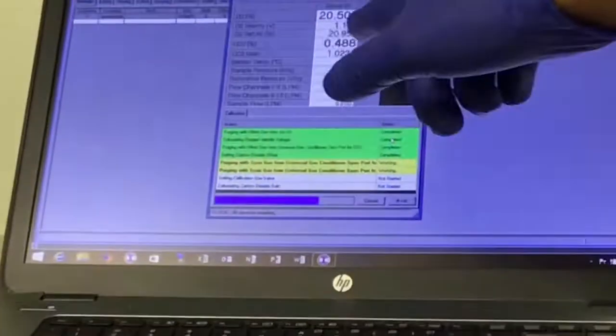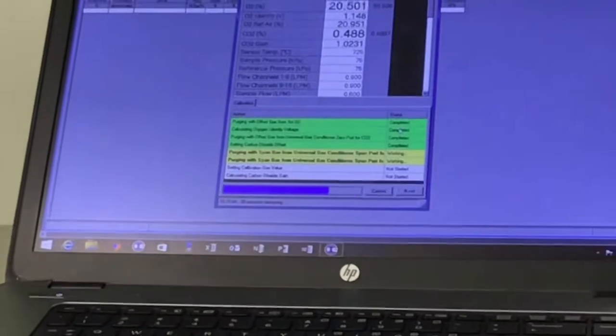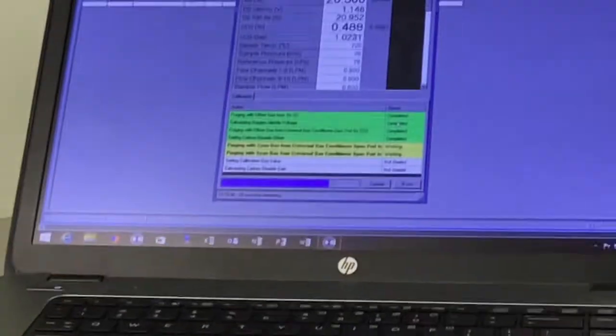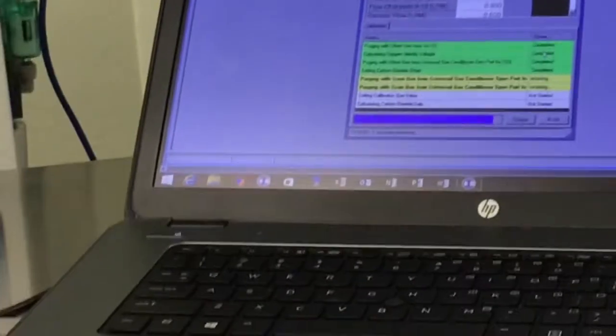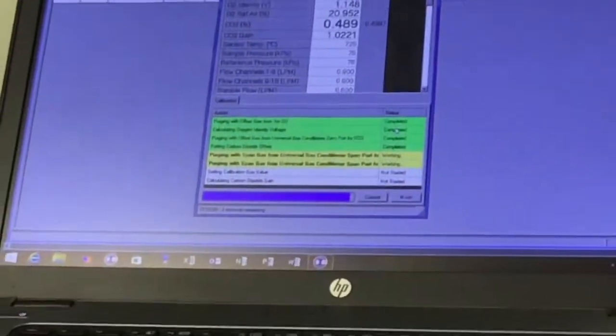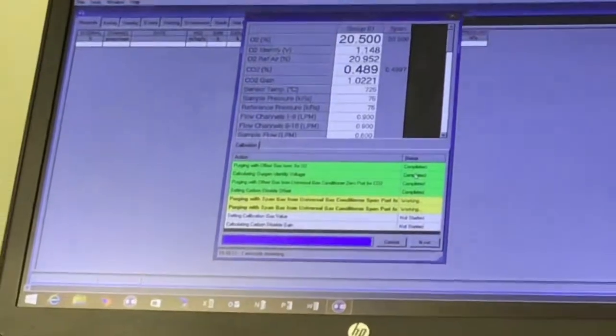Especially the last step is just calculating the gain. The important thing about calibration is that at the end, it should never say it failed. The first thing to look at is the 10 psi, that the gas is plugged in. If you have a calibration process where the gas is on at 10 psi, and you have big problems, you won't see them now, but in two to three years, once it's time to service.